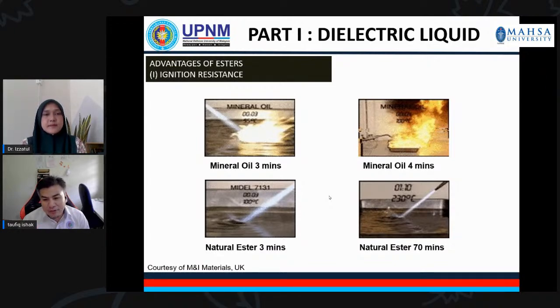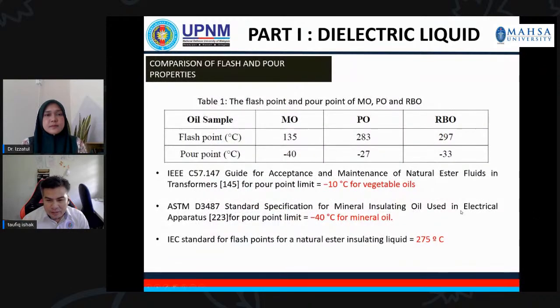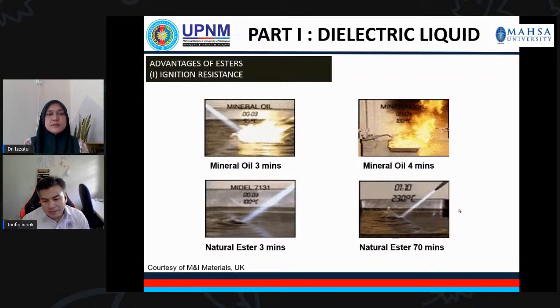There is still no ignition for natural ester at 100 degrees C, and it was tested until 70 minutes. We then raised the temperature to 230 degrees C, and the fire still has not ignited for natural ester. This is the advantage of natural ester, whereby, as I mentioned earlier, the transformer is located near a populated or congested area, or inside a shopping mall and so on. When we use this kind of natural ester, even at a temperature as high as 230 degrees C, and even when we hold that temperature up to 70 minutes, there is still no ignition. This is good for fire prevention for that particular transformer.